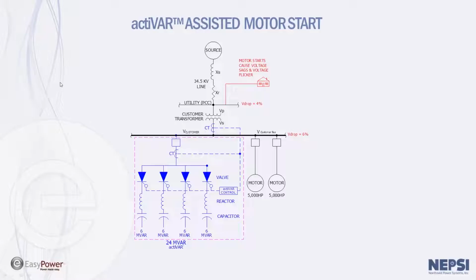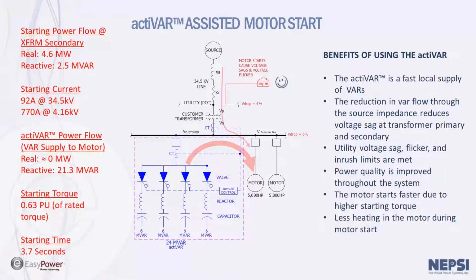Pictured here is the actiVAR assisted motor start, and it operates similar to this function. When the motor starts, the CT here senses reactive power flow through the system, and the thyristors located here will fire to energize those four 6 megavar capacitor banks. So we're essentially supplying reactive power locally to support the voltage. And if you recall, we had a 17% voltage drop before. Now we're at a 4% voltage drop, which was the utility voltage sag limit set on this customer. So we're supplying VARs locally here rather than having the utility supply the VARs, and therefore we reduce the voltage sag through the system. You can see here that we've increased the real power flow from before, and we significantly reduced the reactive power flow through the system.